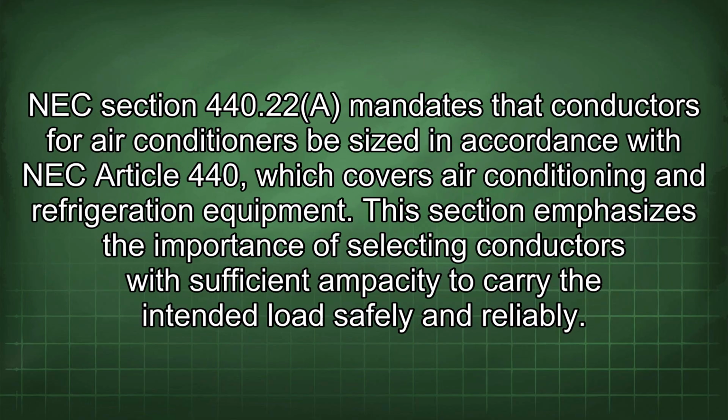NEC Section 440.22 mandates that conductors for air conditioners be sized in accordance with NEC Article 440, which covers air conditioning and refrigeration equipment. This section emphasizes the importance of selecting conductors with sufficient ampacity to carry the intended load safely and reliably.